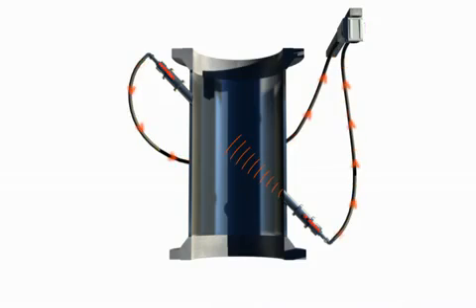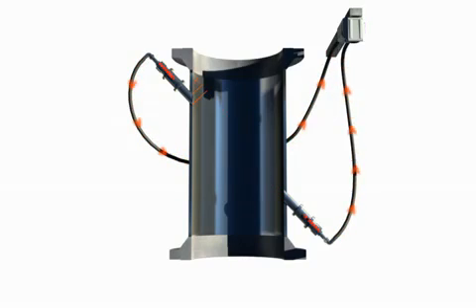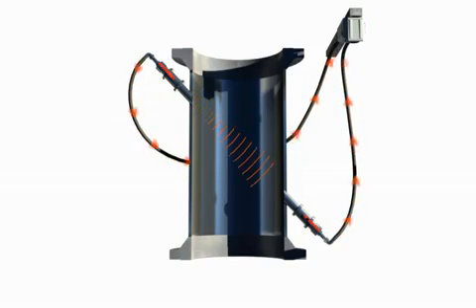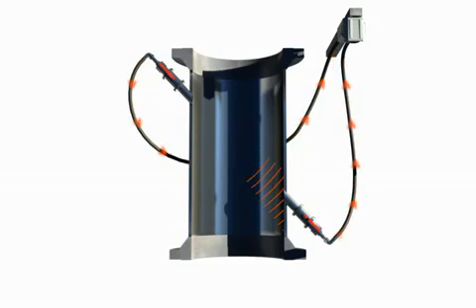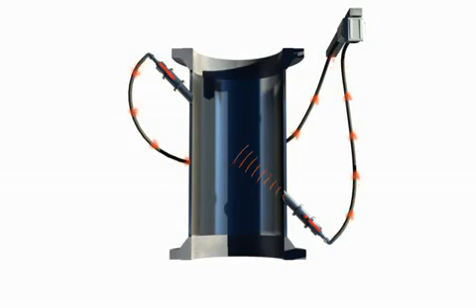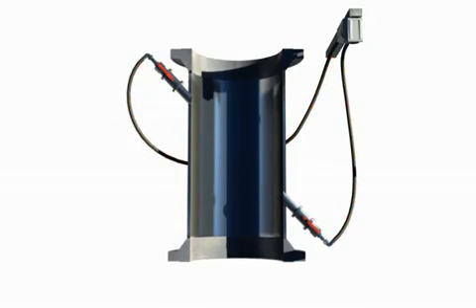When gas is flowing in the pipe, the pulse travelling against the flow takes longer to reach the opposite transducer than the pulse travelling with the flow. This time difference is used to calculate the flow in the flare line.